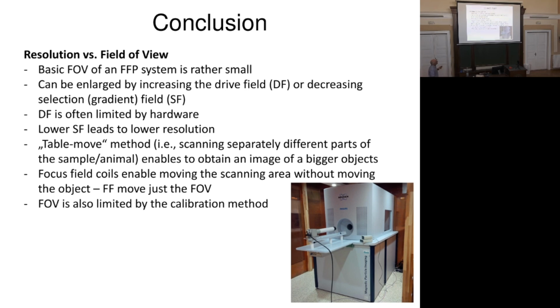Field of view also itself is limited by the calibration method, therefore if you want to scan bigger areas, you really need either focus field or table move method.